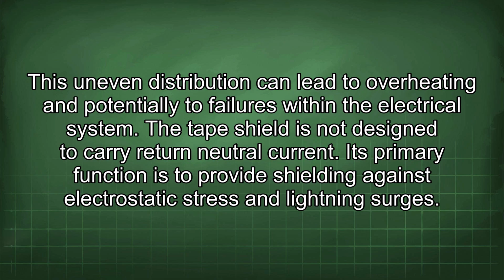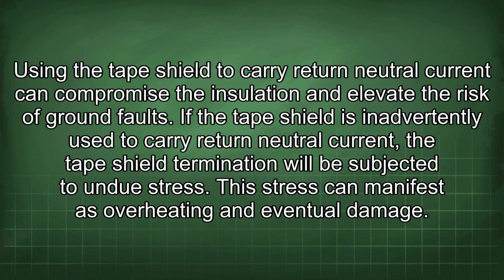The tape shield is not designed to carry return neutral current. Its primary function is to provide shielding against electrostatic stress and lightning surges. Using the tape shield to carry return neutral current can compromise the insulation and elevate the risk of ground faults. If the tape shield is inadvertently used to carry return neutral current, the tape shield termination will be subjected to undue stress. This stress can manifest as overheating and eventual damage.